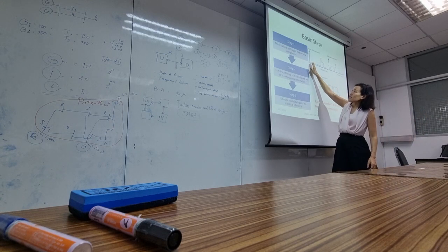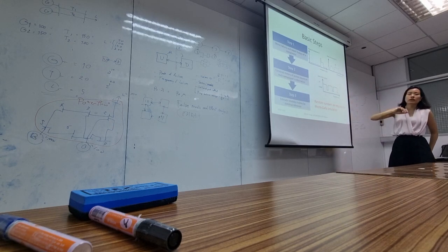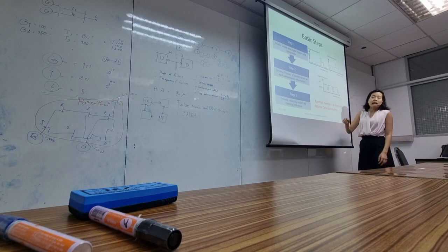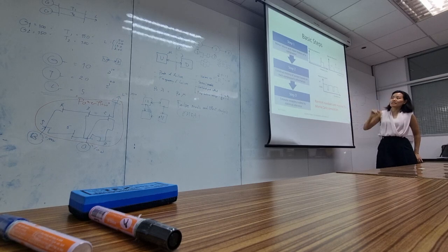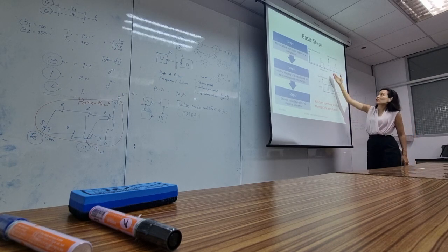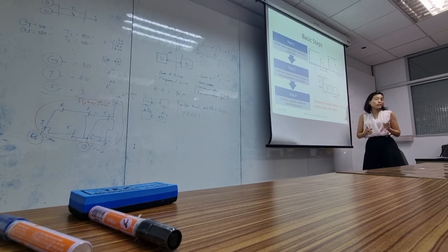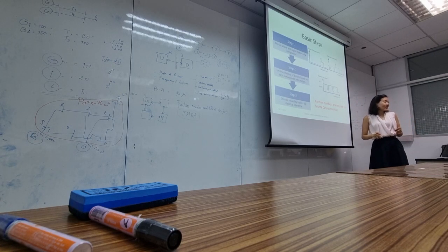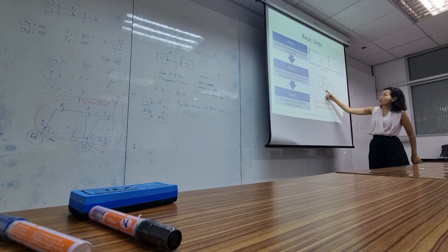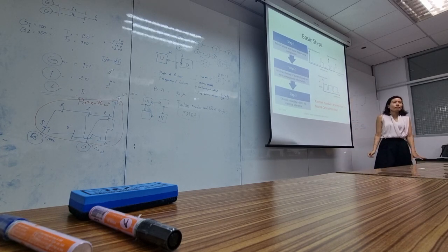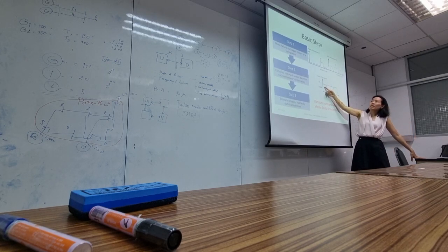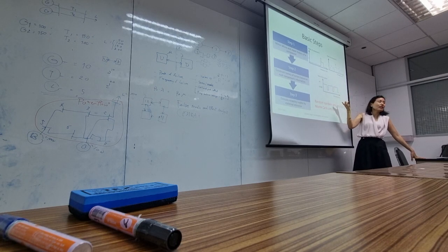We need to mimic the failure and repair history of each component, and from that history construct the system. How do we construct it from this step to this step? You need to know the topology. Okay? And then, if you have the status like here, you just estimate it using statistical inference, what we had earlier. What is the mean downtime? You observe the system when it's down, and then you add them together.